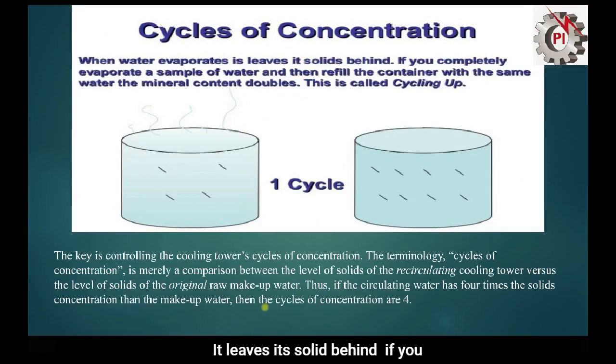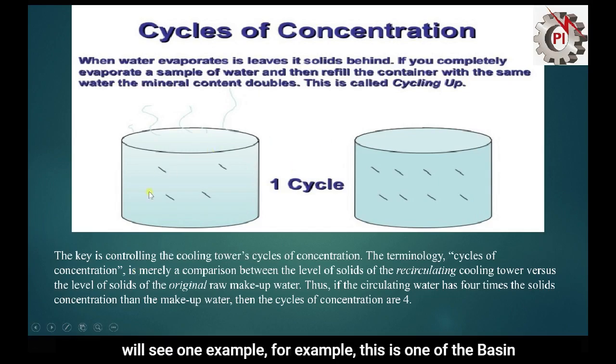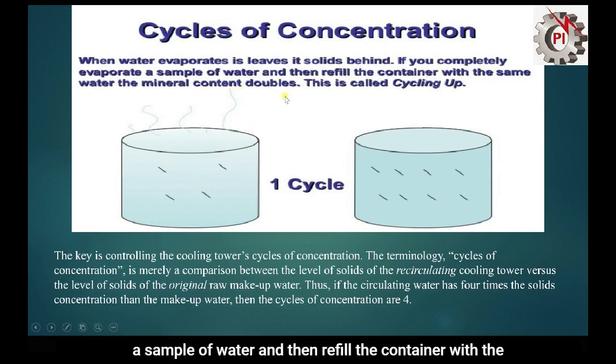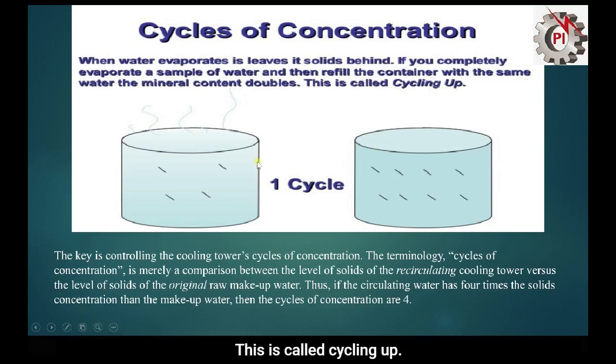When water evaporates, it leaves its solids behind. If you see one example, for example this is one basin. If 100% of the water evaporates from a sample of water and then we refill the container with the same water, the mineral content will be double. This is called cycling up.